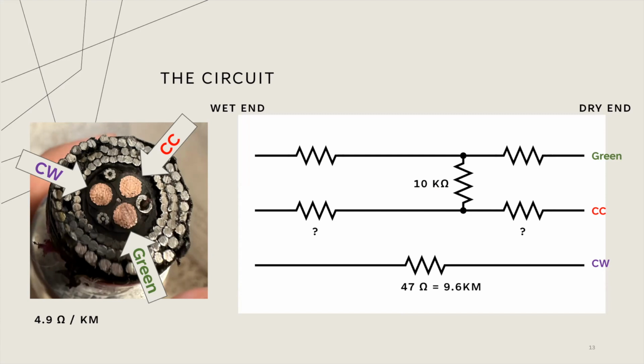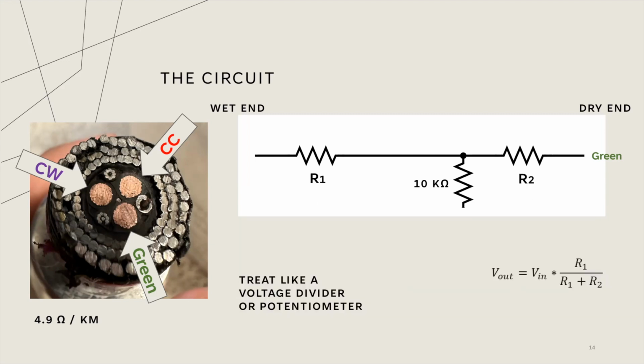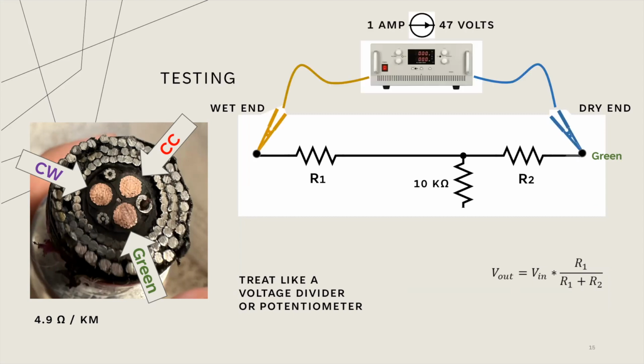So if we can figure out what the resistance is of the cable on either side of that fault, we can use this to calculate the distance to the fault. So if we treat, I've simplified this already simplified drawing even more, just down to one of the conductors included in the fault. We call the two resistances R1 and R2, and we treat this like a voltage divider or potentiometer. So this is the equation over here: V out equals V in times R1 over R1 plus R2. Stick with me here, gonna go through some math.